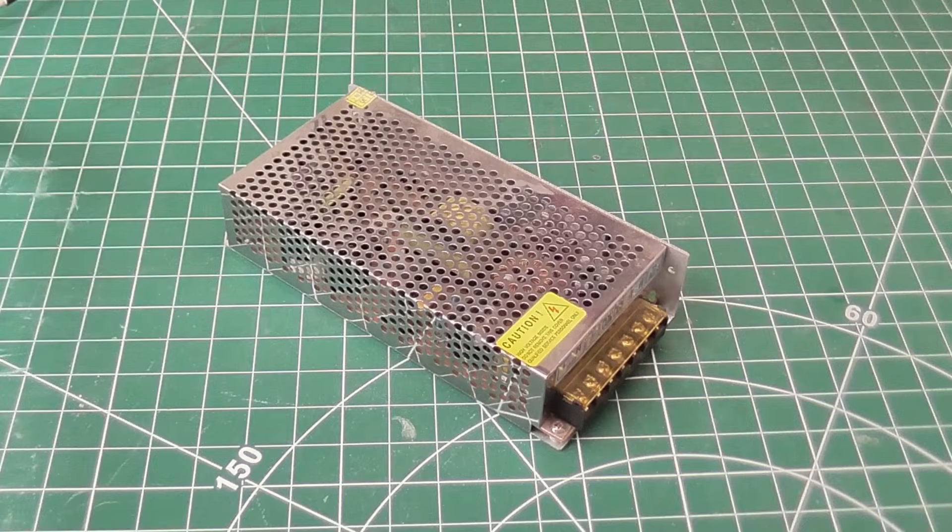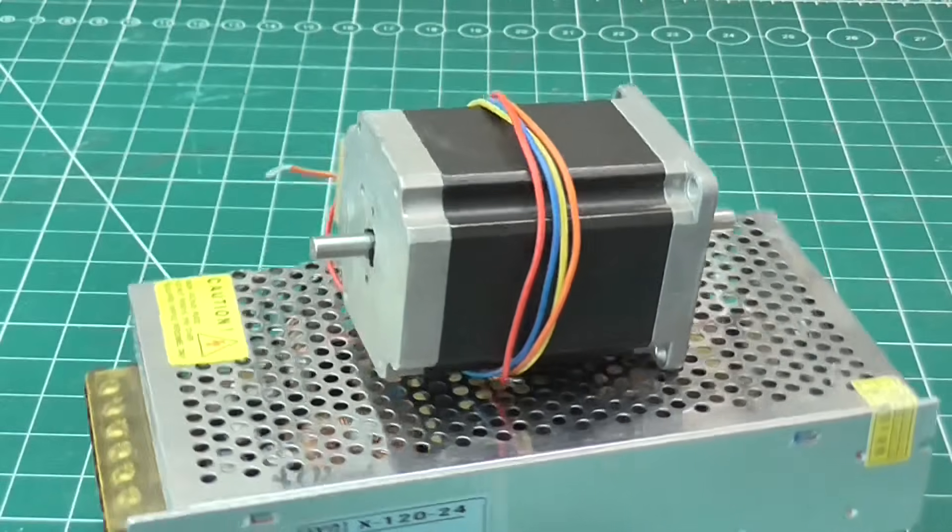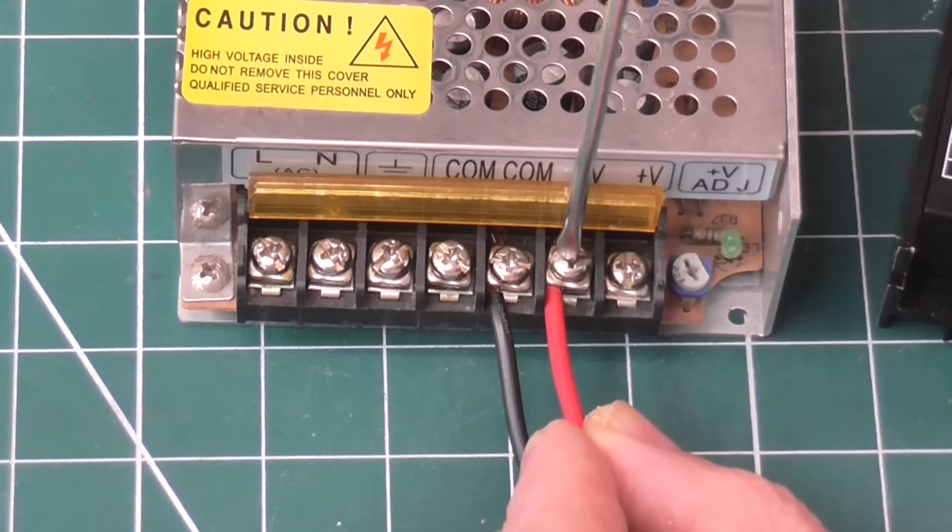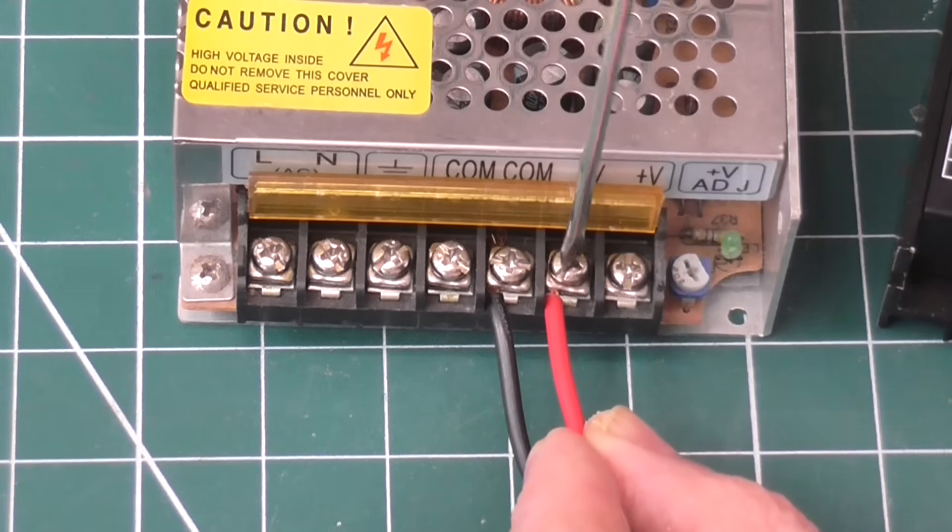Let's approach this a different way. I have this 24 volt power supply that's rated at 5 amps. Surely that should power one 2.8 amp motor. I'm going to connect the driver and motor to this, and measure how much current it actually draws under different conditions.